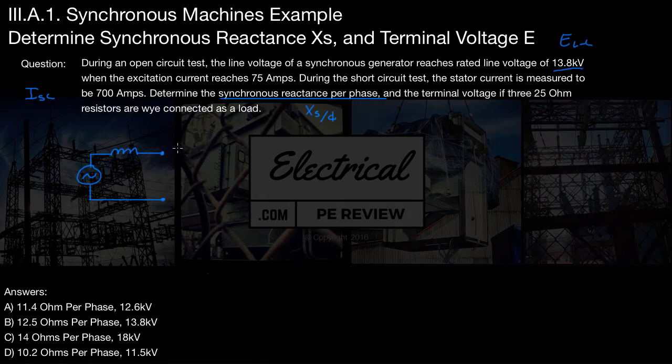Now, since this problem is asking for Xs per phase, that means that this right here has to be our neutral. And up here, this is going to be our phase. So that means that our 13.8 kV, our line-to-line, has to be divided by the square root 3. And this gives us a line-to-neutral value of 7,967 volts.